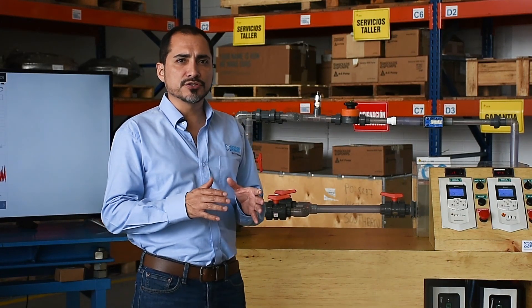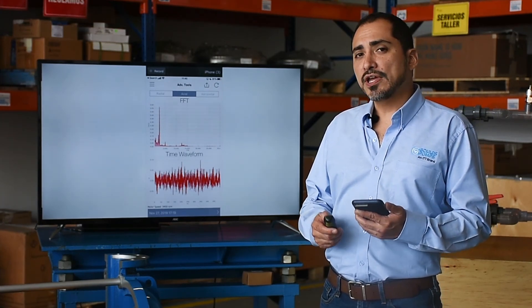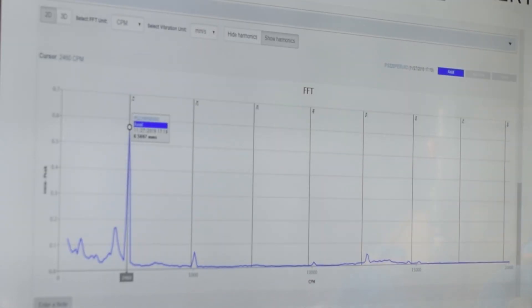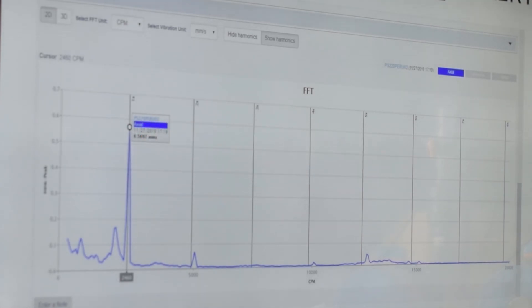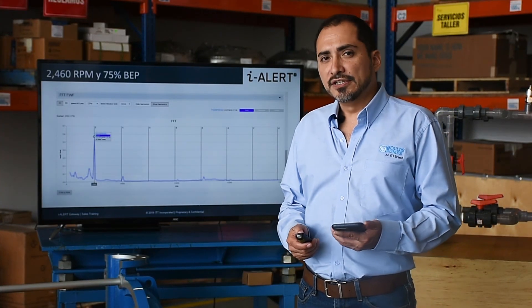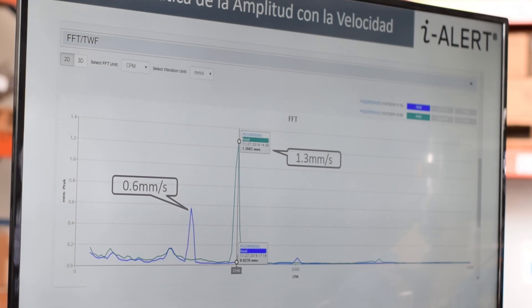We want to show the same operating condition close to the BEP, which we saw at the beginning, but this time at 2460 RPM. Jesús asked for an FFT and let's see what we get now with the aid of the i-ALERT platform. We see that the first peak has shifted from 3500 to 2460 CPM and the peak in the vane pass frequency went from 14,000 to 9840 CPM — something logical, maintaining linearity with the speed of rotation. However, something more interesting is what happens with the amplitude, which is reduced with the square of the speed. Looking at a comparison between these two FFTs, at the speed of rotation the amplitude went from 1.3 to 0.6 mm per second, so the quadratic relationship between the amplitude is confirmed.